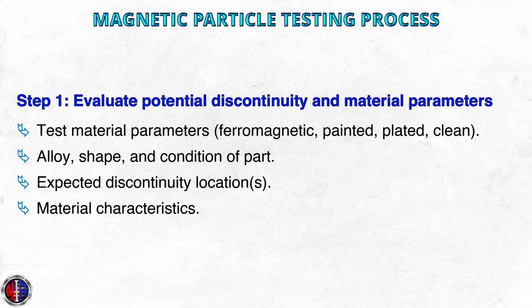Paint and plating. Is the material painted or plated? Thin layers of paint and certain plating substances may be acceptable, however clean bare metal provides the best results. Some codes and specifications require a qualification process to ensure that plating or coating will not adversely affect the test. Cleanliness. Is the material clean enough? Contaminants and corrosion can degrade the magnetic particle bath solution and inspection sensitivity.